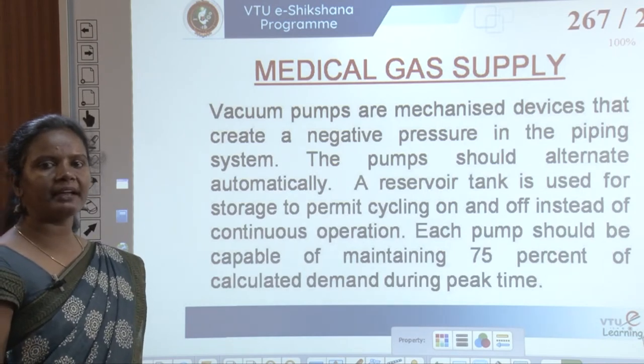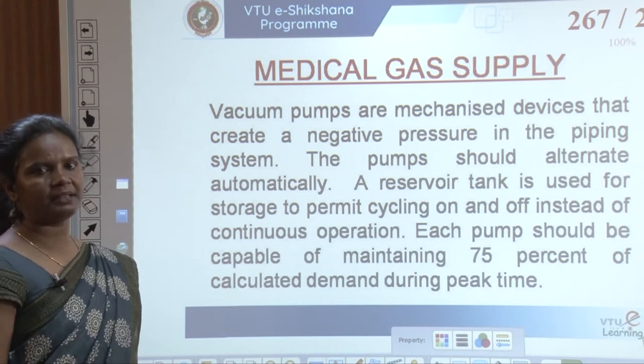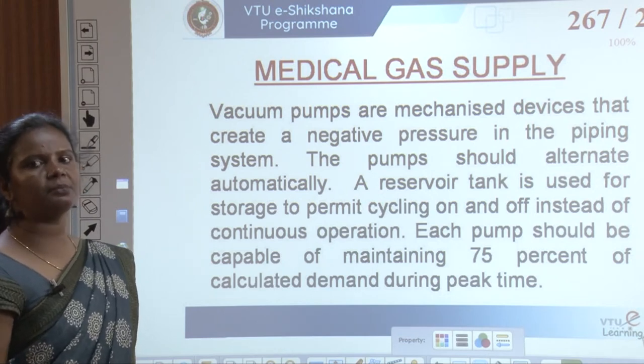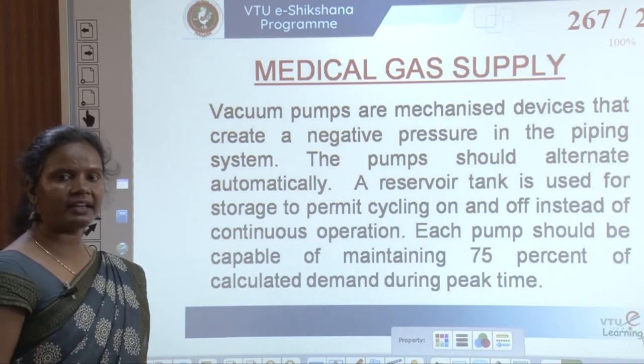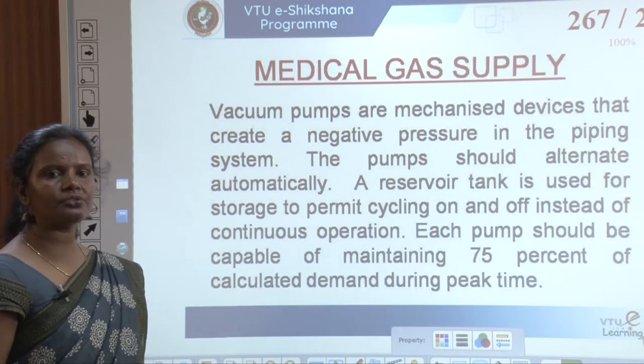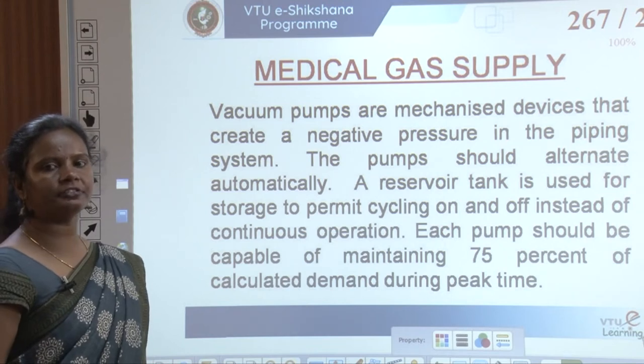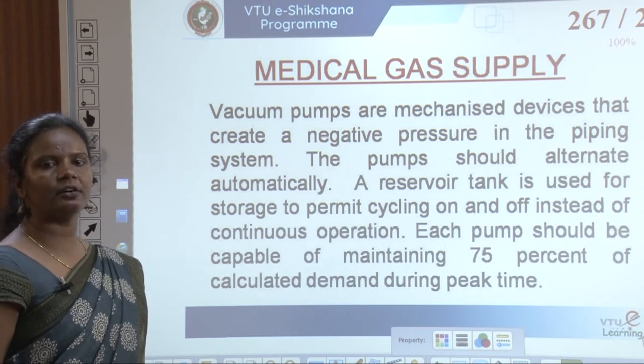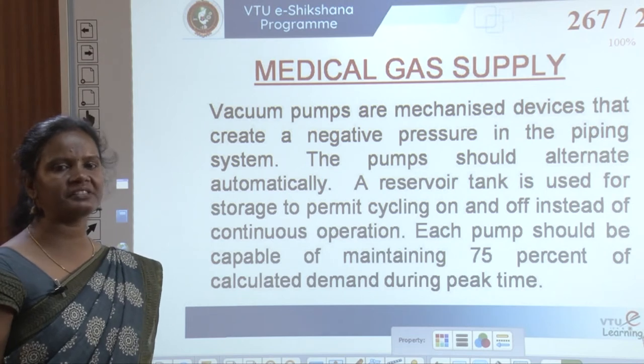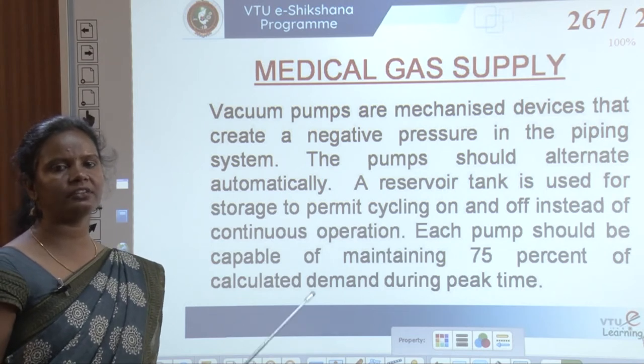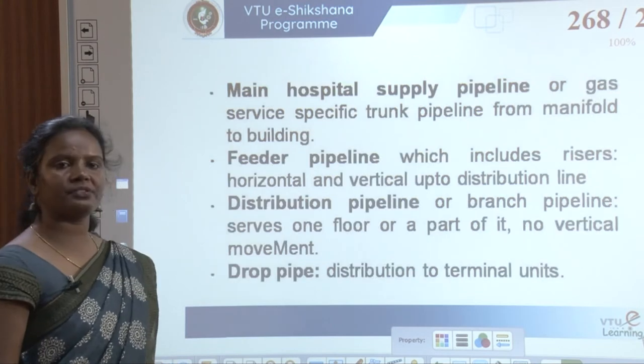Vacuum pumps are mechanized devices that create negative pressure in the piping system. The pumps should alternate automatically. A reservoir tank is used for storage to permit cycling on and off instead of continuous operation. Each pump should be capable of maintaining 75% of calculated demand during peak time.